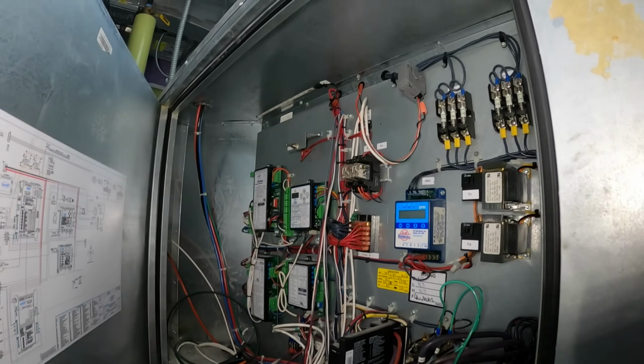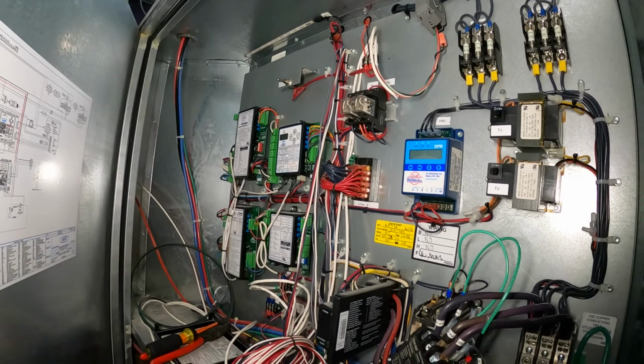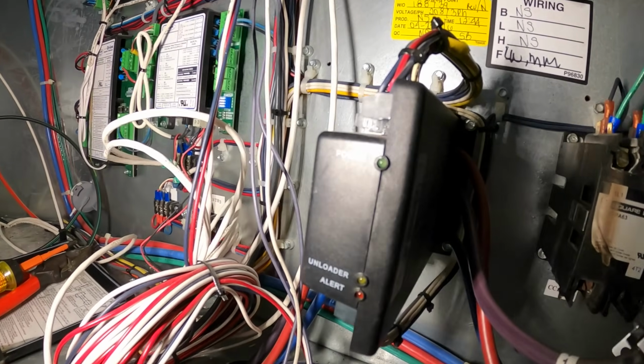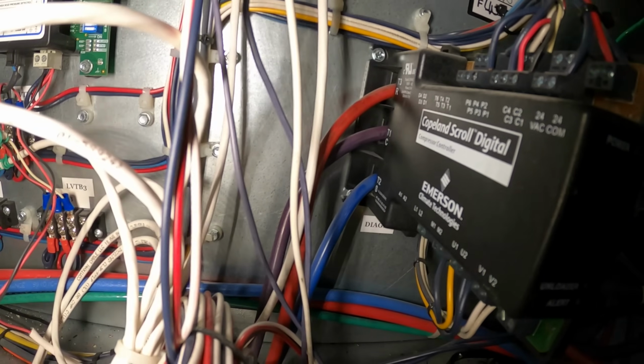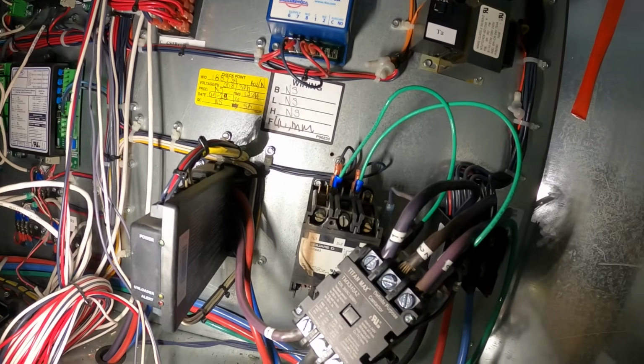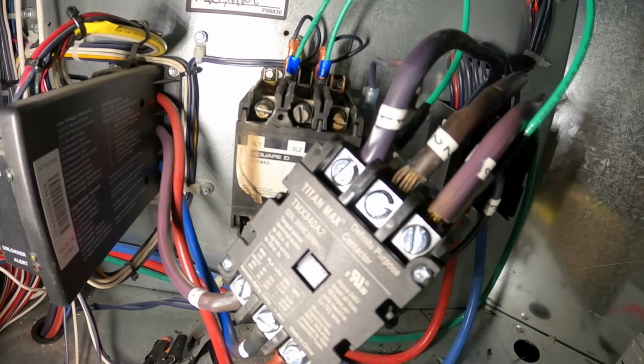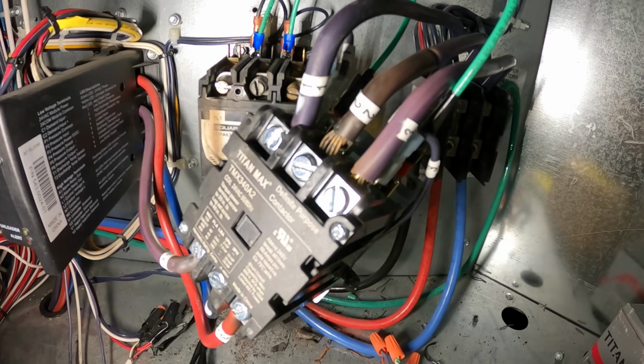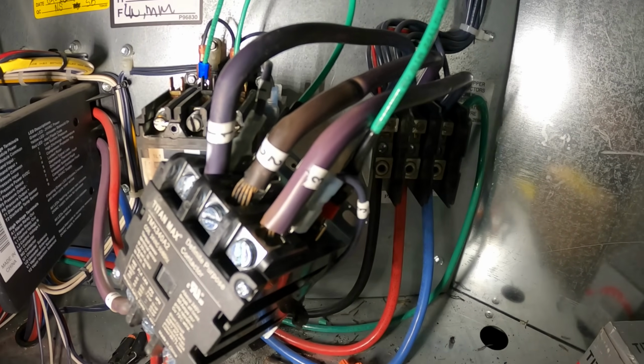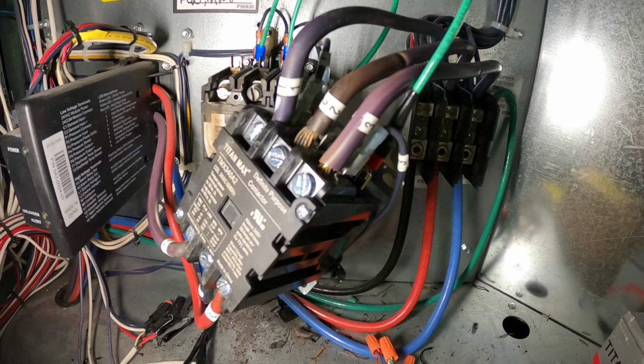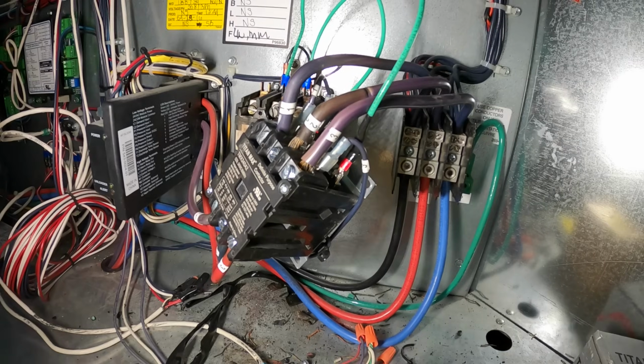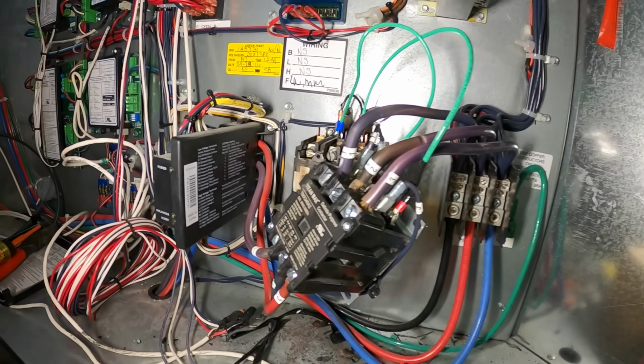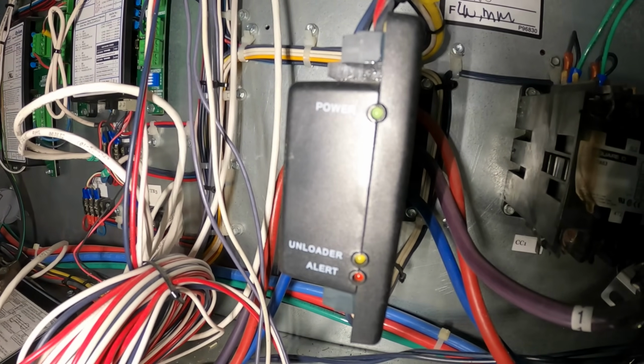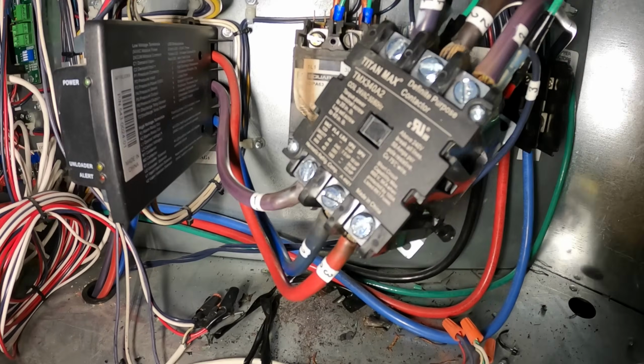We are currently in the control panel. This is a follow-up service call for an AAON water source heat pump. In my last visit, we had an alert here for this unloader and the system wasn't working. What I found is that this contactor, as you can see, burnt out. I put this in and I have everything labeled 1, 2, 3. When I put this on just as a test, the alert went away, because it seemed that there was no compressor connected, because we lost the phase here.